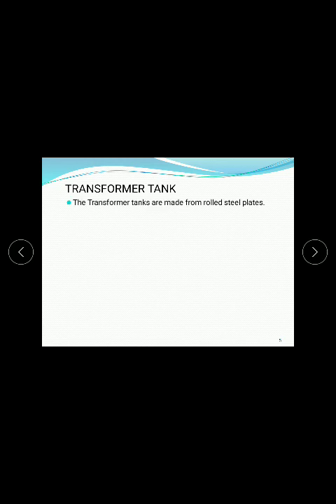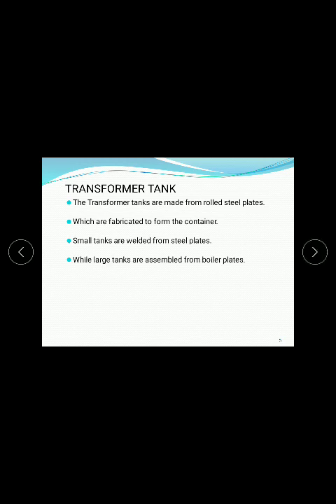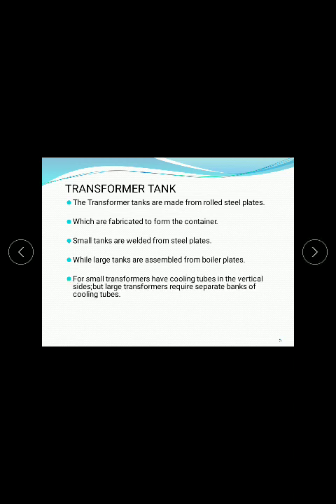The transformer tanks are made from rolled steel plates, which are fabricated to form the container - meaning the oil box tank. Small tanks are made from steel plates, while large tanks are assembled from boiler plates. Small transformers have cooling tubes on the vertical sides, but large transformers require a separate bank of cooling tubes.